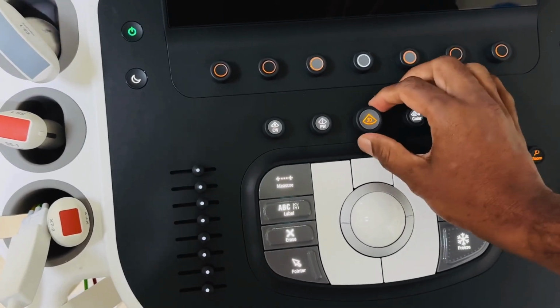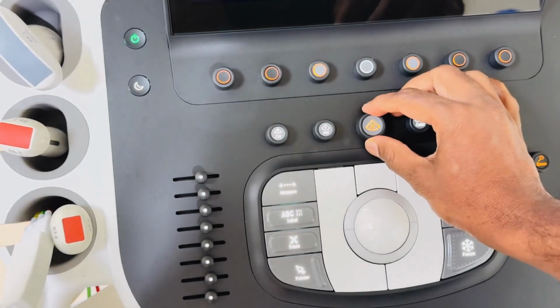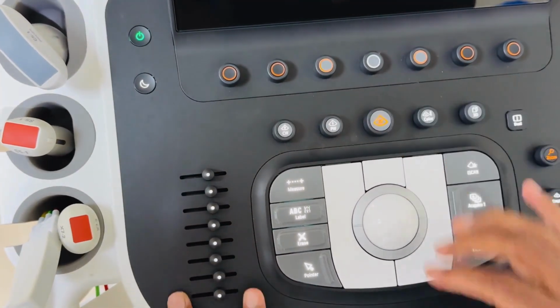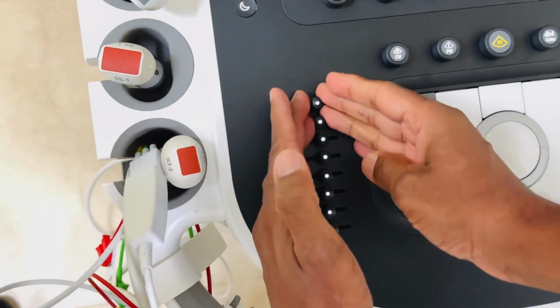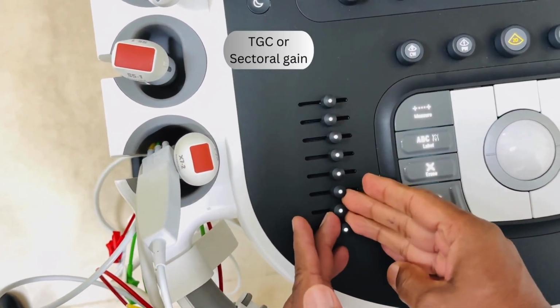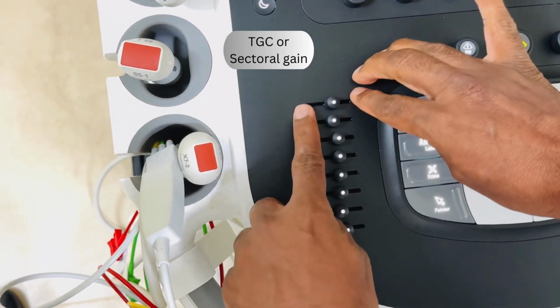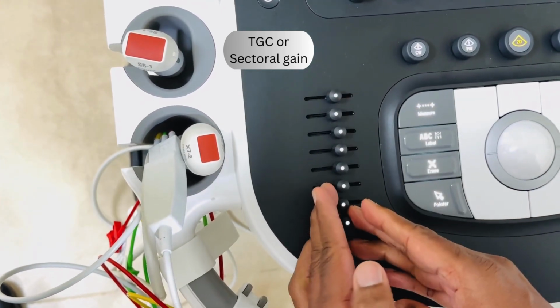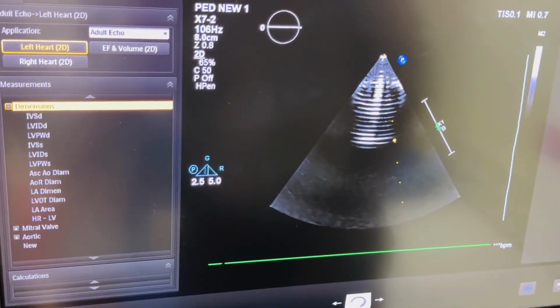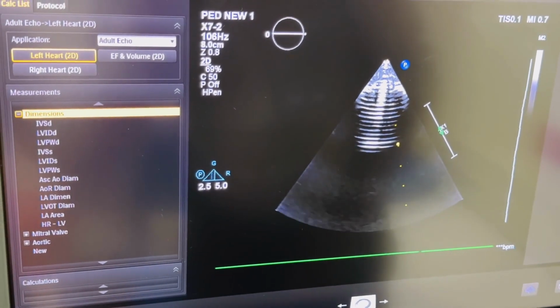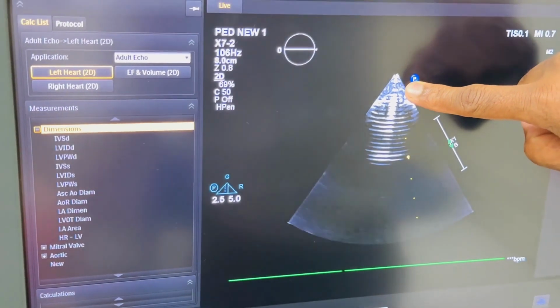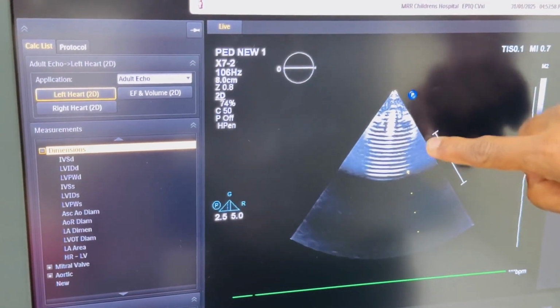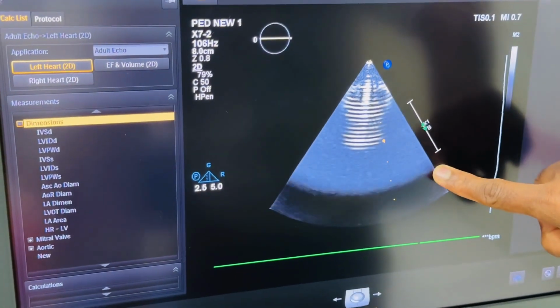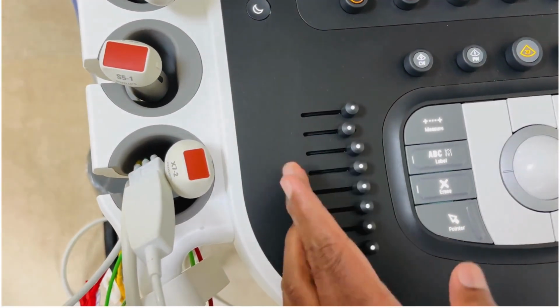So we saw that the gain button is fixed on this machine on the 2D knob only, but there are also a few additional knobs, and these are called TGC or sectoral gain. So basically you can adjust the gain of each and every sector on the screen based on these knobs. So as you can see here on the screen, now the gain is very less. Now I start moving the knobs. The top two knobs will increase the gain in the top triangle. Then the next two knobs will increase the gain here. The next two knobs will increase it here, and then the next two will be here. So as you can see now, all the knobs have come completely to the right side.